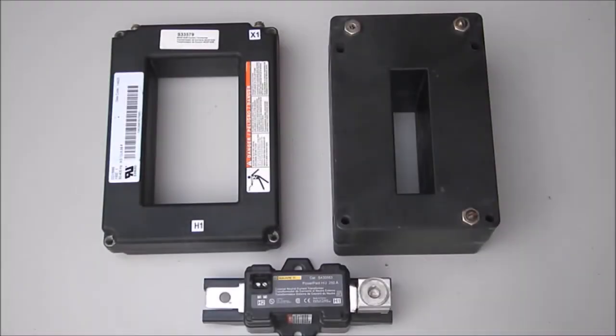Now regarding neutral current transformers or NCTs. NCTs are a special type of current transformer specially designed to measure neutral currents and report the results to electronic circuit breakers and ground fault or GFI system electronic inputs.